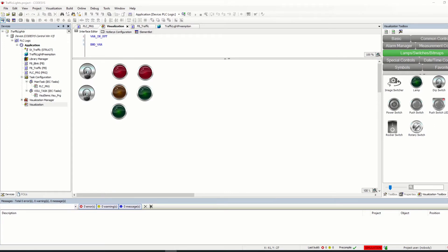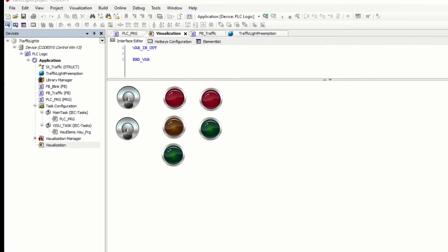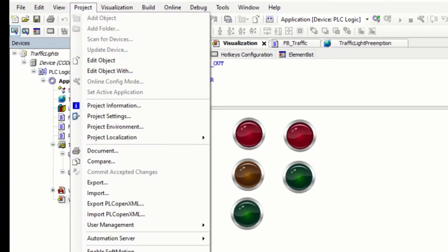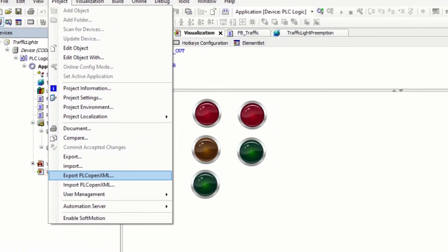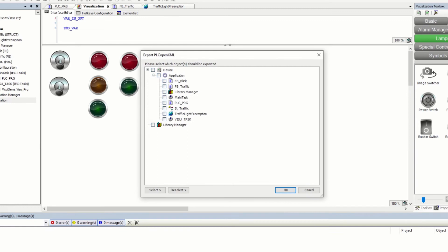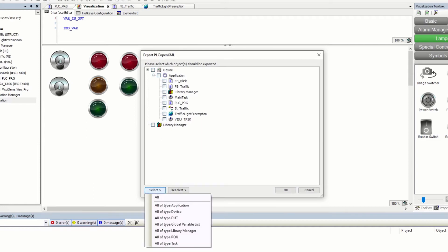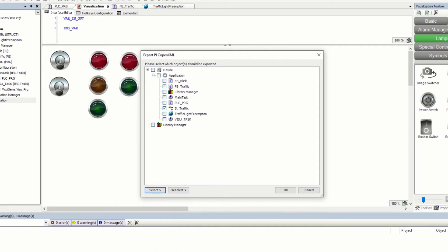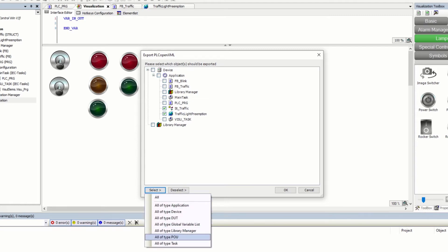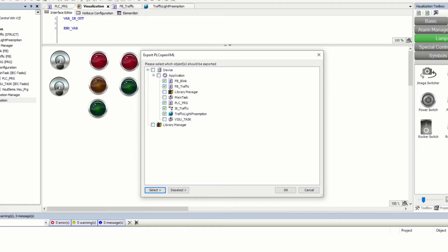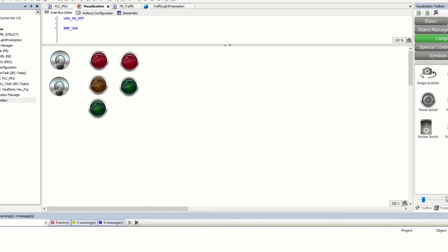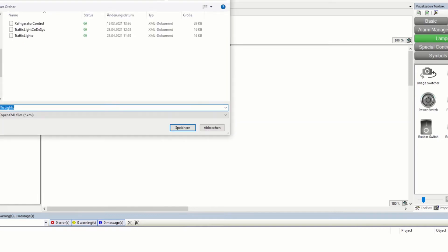After the logic test, I will start exporting this code via PLC OpenXML to import that file into my Guide project. The first step is to select Project > Export > PLC OpenXML. Inside the PLC OpenXML dialogue, you have to select which objects should be exported, because not all objects can be imported and used in Guide. The easiest, fastest and safest way is to select specific types: all of type DUT (data unit type), all of type global variable list, and all of type POU. These types can be handled by Guide; the other types are more CODESYS or PLC tool specific. The CODESYS code is then exported into a PLC OpenXML file stored on your disk.